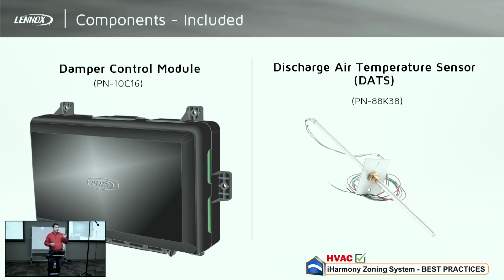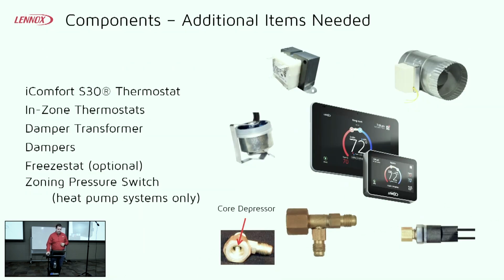And so it's really important that we get that installed in a proper spot, where sometimes that can happen in the ductwork where you might have a dead spot in there, or a colder spot or a warmer spot, and that's what a lot of times can cause some havoc in how the system operates and staging the equipment. Either it's not staging up enough, or it's overheating. Sometimes that's just an issue of where the discharge air sensor is located. We'll touch into that a little bit later on.